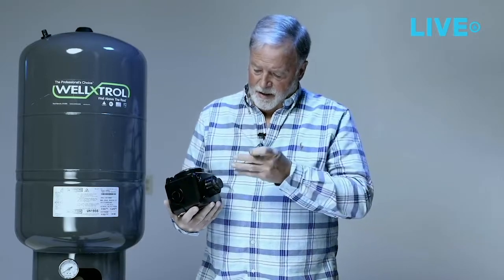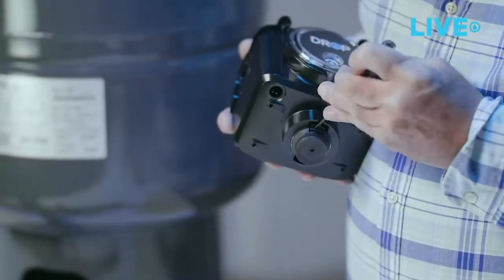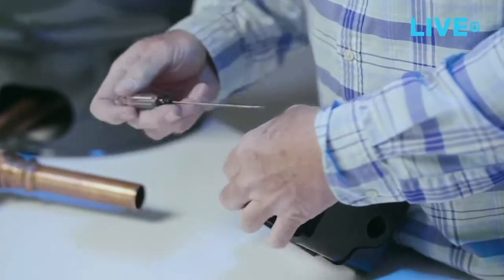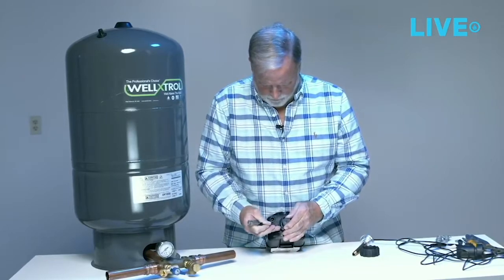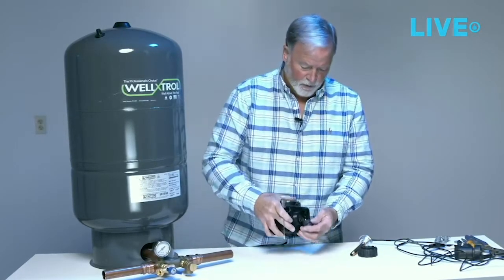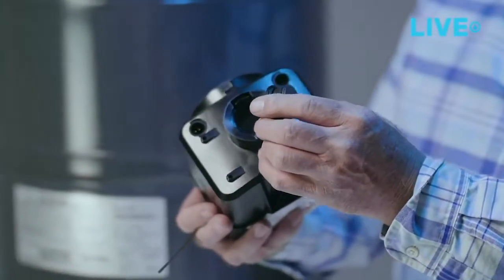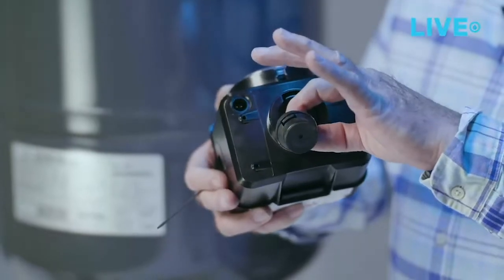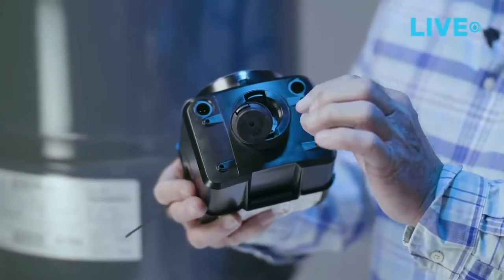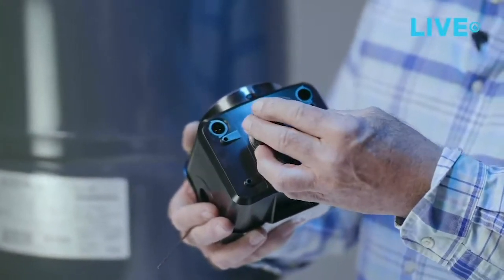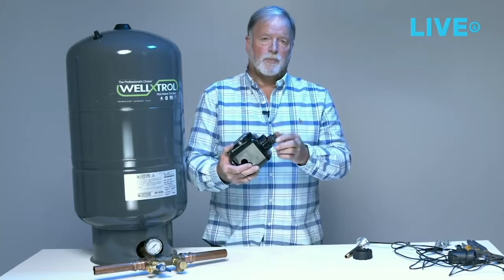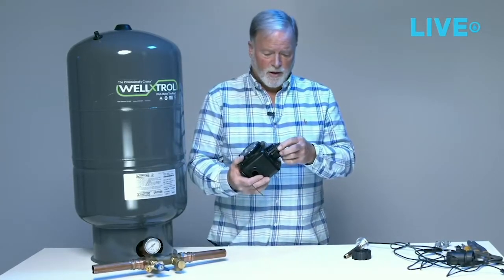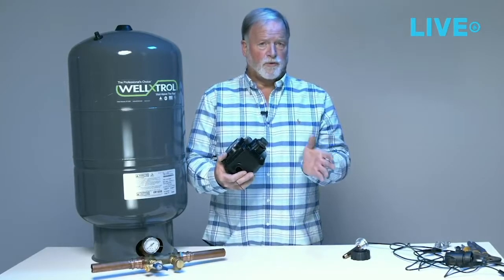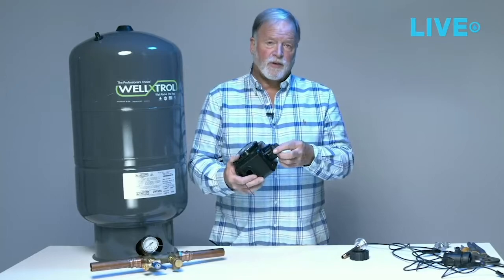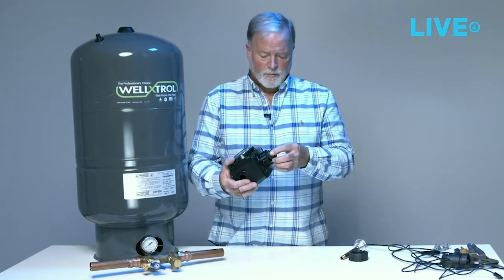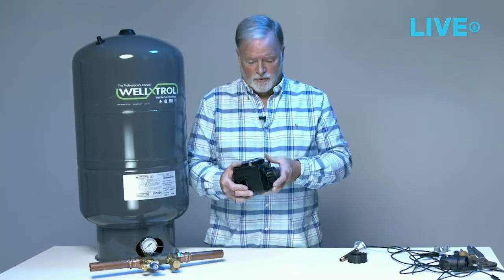While I have it in my hand, I want to show the transducer. So this is the pressure transducer. Like I said, we make the whole thing at CSI. It's a pressure-sensitive electronic chip, and then we wrap it in silicone and seal it off with an elastomer diaphragm. So it's completely protected from any of the contamination in the water. I know there are some transducers out there that just take the water directly to the transducer, and it's important that you see that not only is it serviceable and replaceable, but we build it at a very high standard to protect it from the elements.